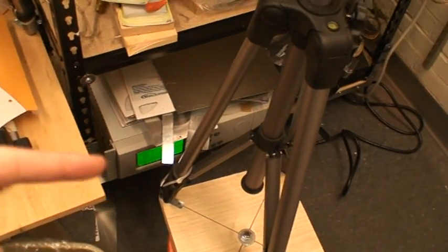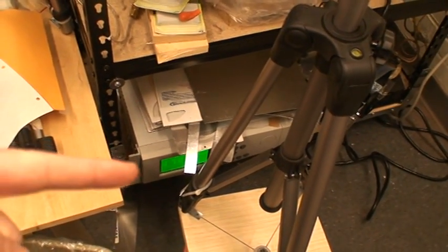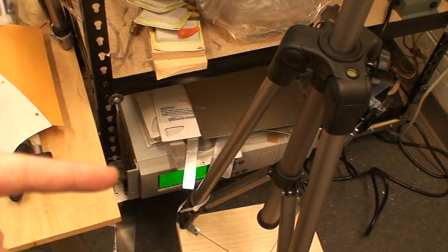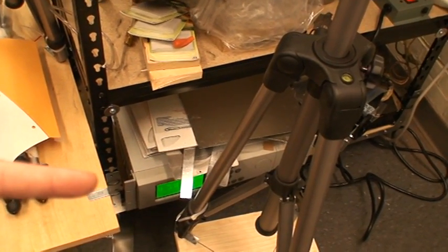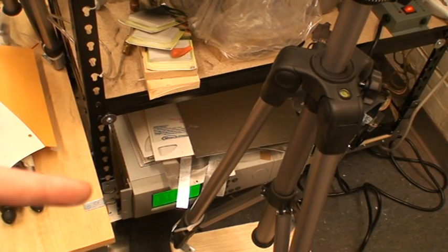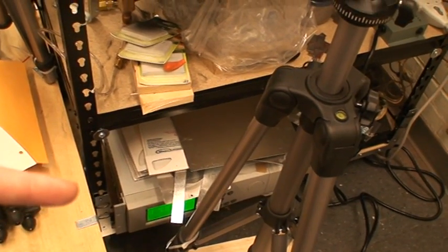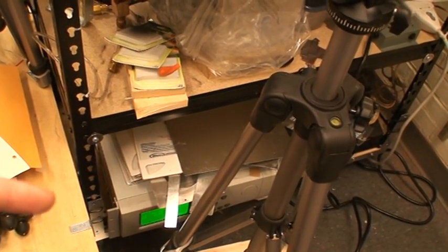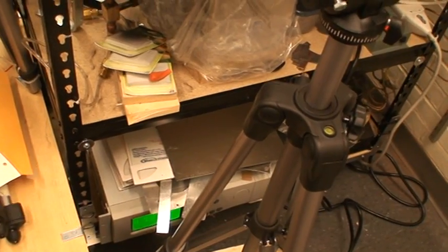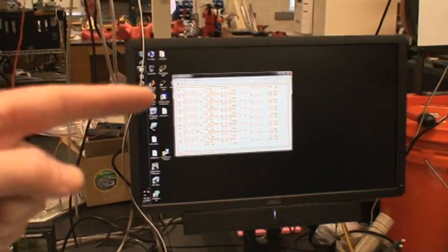So when we set up the Servomex analyzer here, we want to set it to a continuous output, the baud rate is 9600, and there's no parity. But whatever you set this unit to, you want to set your HyperTerminal to be the same thing.